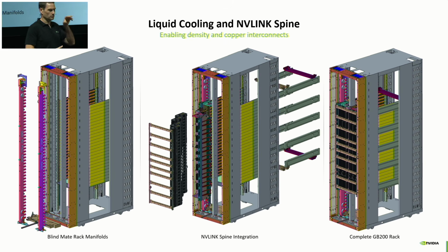We take that manifold and position it in the center of the rack, very deliberately, off of datums that are centerline of the manifold. The reason is the coefficient of thermal expansion of stainless steel is actually pretty large at this scale. With this manifold being 2.1 meters tall, going from its ambient temperature of say 25 degrees C to its service temperature of around 75 degrees C, there's a meaningful expansion across that manifold—multiple millimeters.